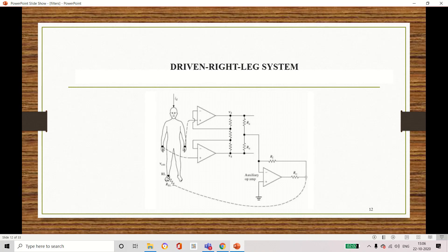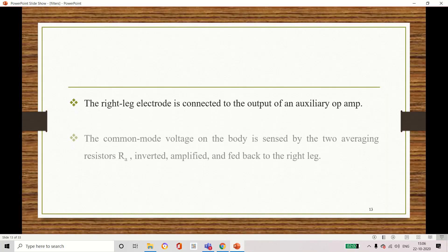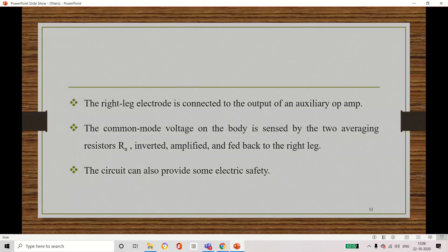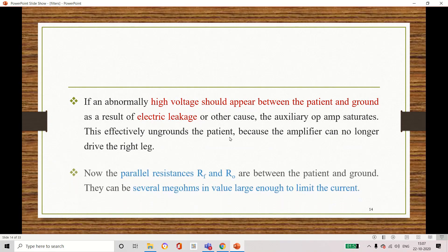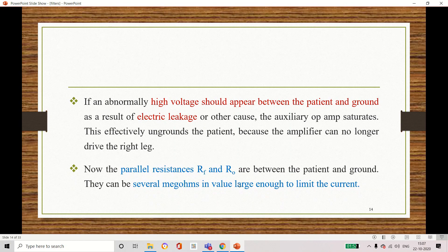The main operation depends on reducing the common mode interference — that is the main application of this right leg driven circuit. This circuit is mainly used to give protection to the patient. If there is any electric leakage between the patient and the ground, it will automatically disconnect and protect the patient. In the circuit, Rf and Ro components have very high values in the range of several mega ohms, so that we can limit the current.